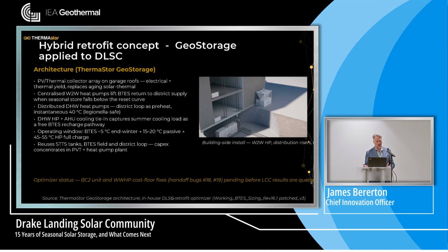So what would it look like if we'd have done a hybrid retrofit, or if we'd just done Drake Landing 3.0, as I like to call it, because we've definitely gone beyond 2.0 already. If we'd have done that from the start, what would we do differently? So we'd have this hybrid system. What were the other things we learned from Drake Landing? The scale. When you change that scale, just by doubling your scale, you drop your surface area to volume ratio. So now you've got a bigger storage, but it's got much less surface area per unit volume. When we do that, we lower those losses. So instead of 45%, if we'd have doubled it, I think I calculated it up to be 65%, and it was 76% if we quadruple it. And quadruple is not huge.